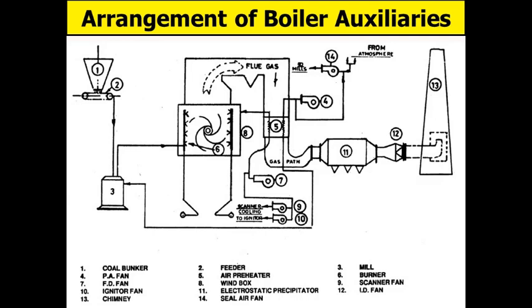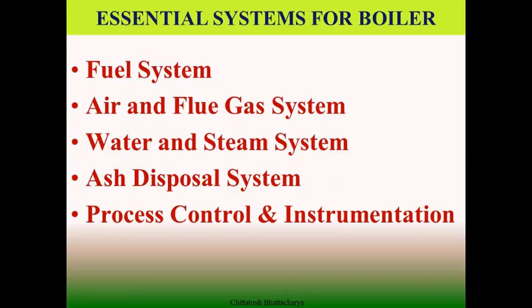Even the residual heat, when the water steam circuit is not absorbing the heat, is absorbed for preheating of air, and post preheating of air, exhaust flue gas is passed through dust and suspended particulate matter separation system so that all the fly ash is arrested and clean flue gas is evacuated with the help of ID fan through the chimney.